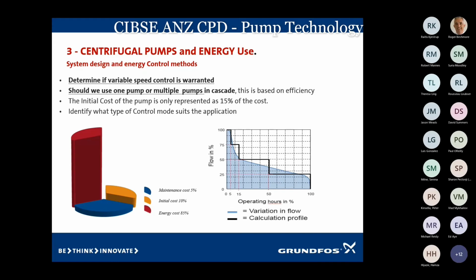In larger systems, as in water boosting and heating and chilled water, is it a good idea to have one pump? Probably not necessarily at all, because as we know now, we try to run the pump in a good area on its performance curve around that best efficiency point. And if you've got a large pump which has a peak of, say, 30, 40, 50 litres a second, but then most of the time it could be running at 10 litres a second, then it's a good idea to split that into 2 pumps or 3 pumps to manage it much better. So as we put in more pumps, then we have a better efficiency, because each pump has its own efficiency, and we can drive that pump to a better point, and then we can save some energy costs.